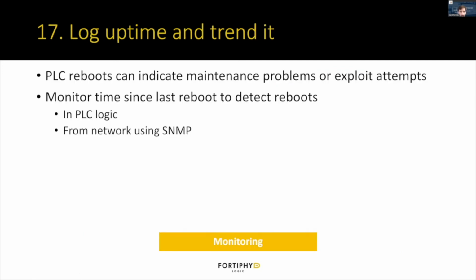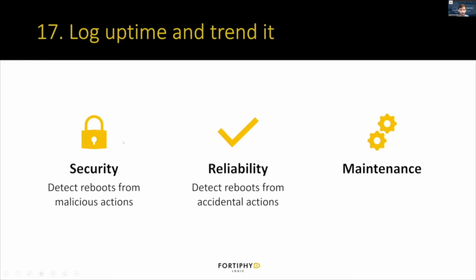Number 17 is logging uptime and trending it. As I mentioned before, PLC reboots can be either a maintenance problem or an exploit attempt, so monitoring when the PLC reboots is important. You can do that from the PLC logic itself, or if the PLC supports SNMP, you can also do that from the network. For security, the benefit is that detecting reboots can indicate potentially malicious actions. For reliability, it helps to detect power loss reboots and investigate why that happened.